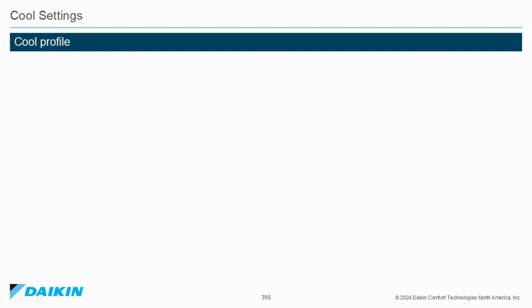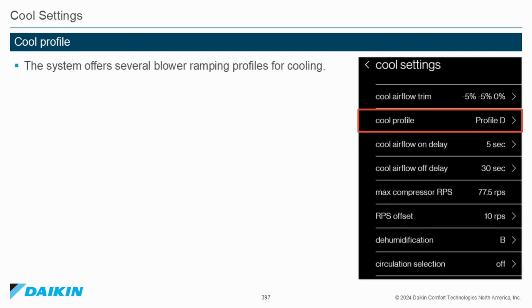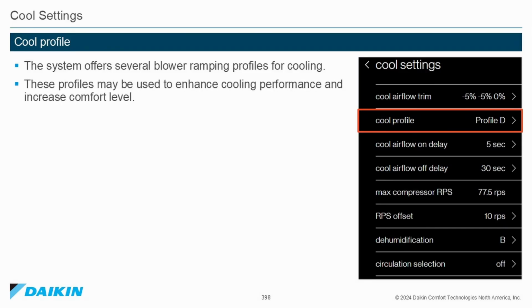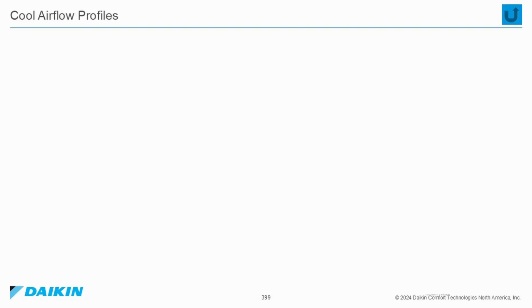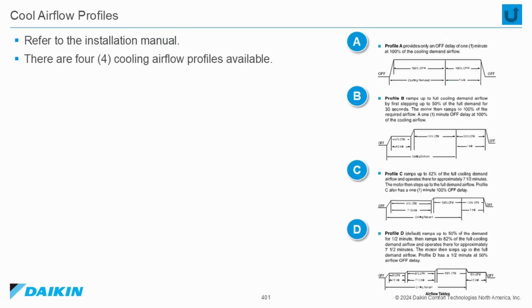Cool profile. The system offers several blower ramping profiles for cooling. These profiles may be used to enhance cooling performance and increase comfort level. Cooling airflow profiles. Refer to the installation manual. There are 4 cooling airflow profiles available. All residential inverter systems are factory set for Profile D.